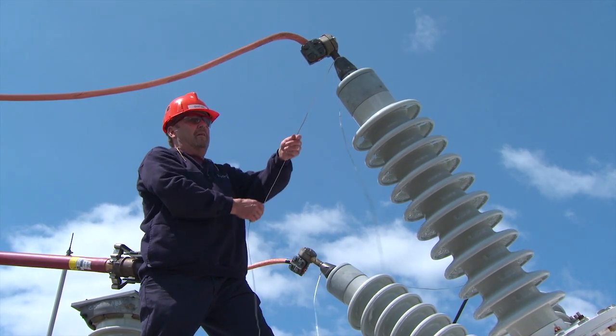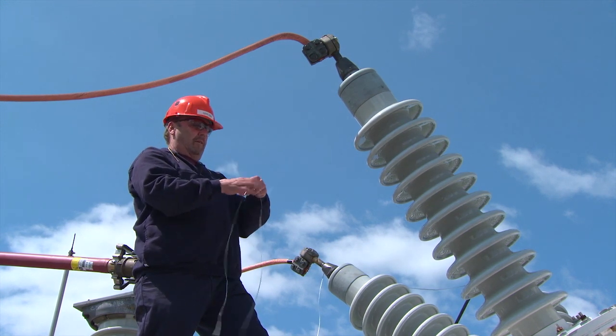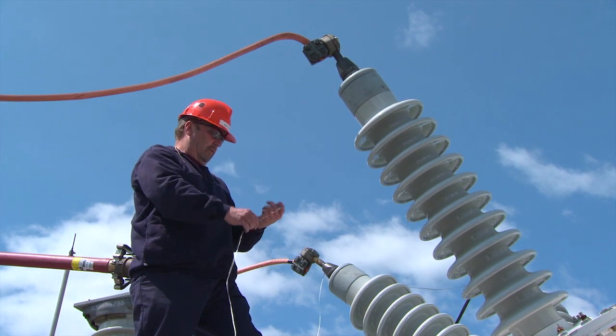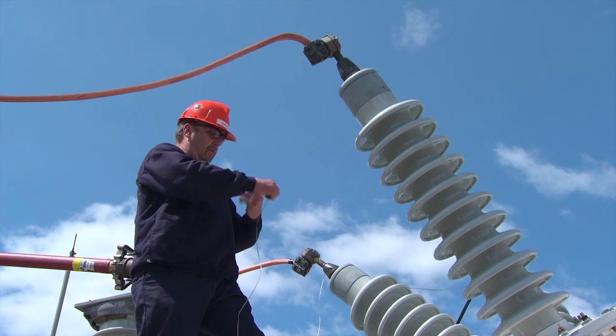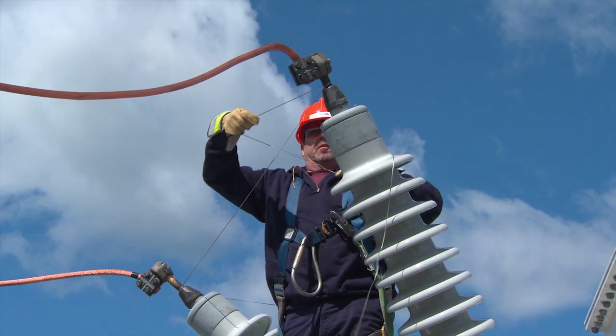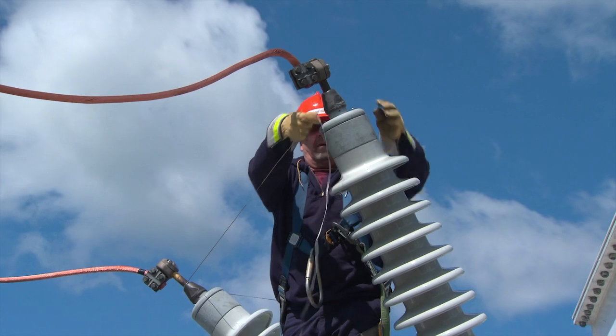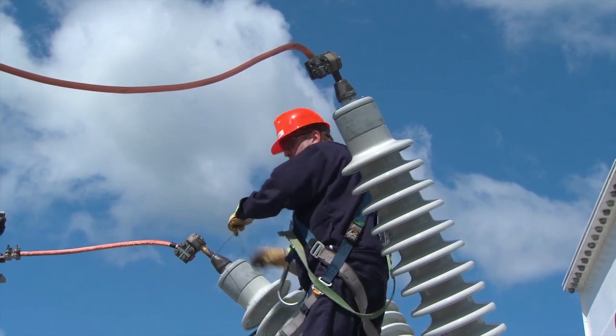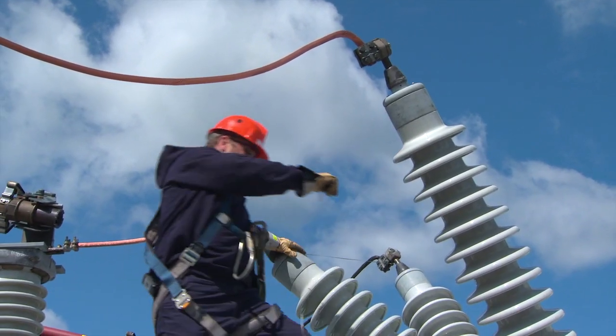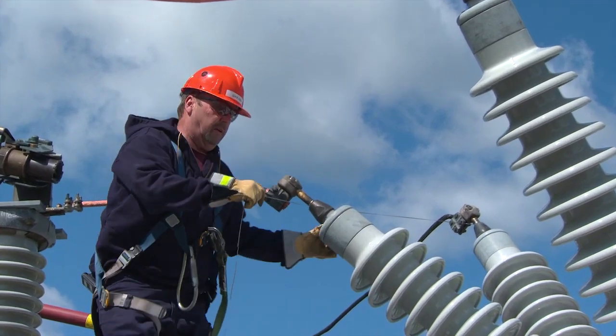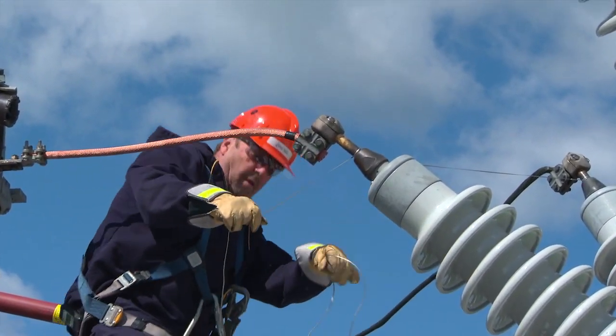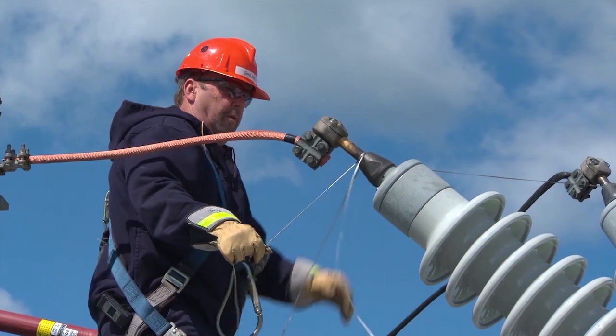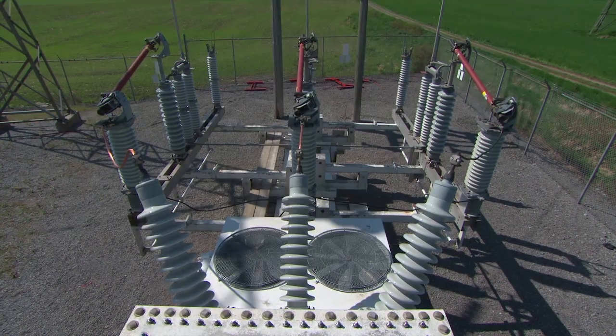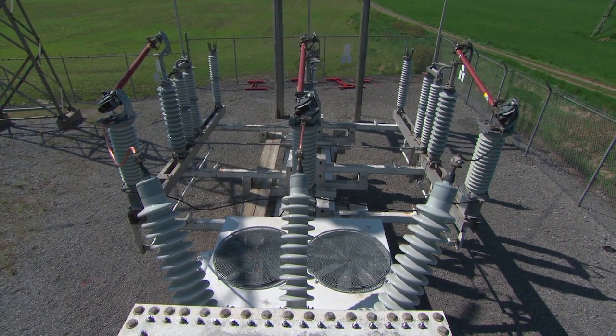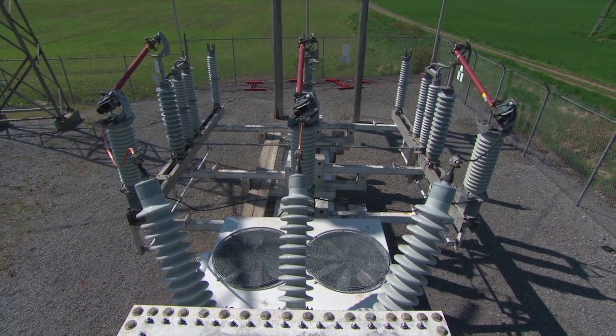Once all tests are complete, remove all wire braid from the low-voltage and high-voltage bushings and reconnect the X0 bushing. Record the ambient temperature and compare all results with the previous test results. Because the bushings are not disconnected for this testing, the high-voltage and low-voltage surge arresters are part of the insulation test. If a bad megger result occurs, the bushings should be disconnected and tested again. The surge arresters should then be tested independently.